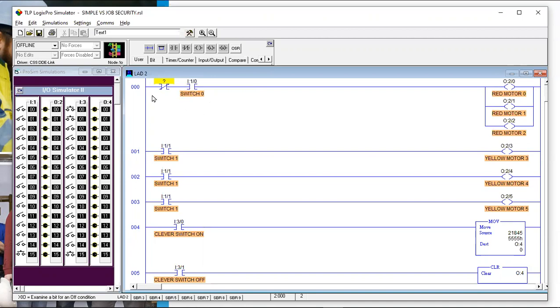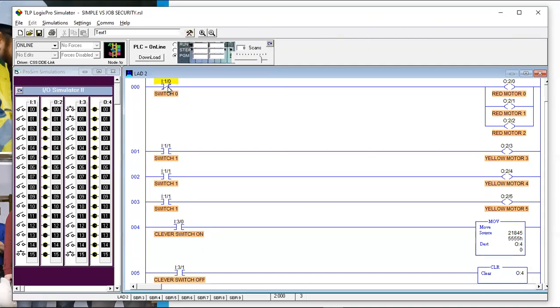When people are first starting out, this is the one that really messes with them. The best way is to demonstrate it. In Allen Bradley it's called an XIO — Examine If Open — meaning examine this switch to see if it's open, and if it's open, this becomes true. My best advice for learning how this works: forget about schematics. Do not look at this like normally open and normally closed, because they aren't. These are not switches — this is an instruction.